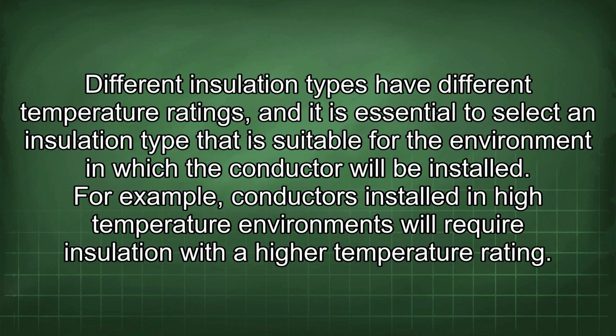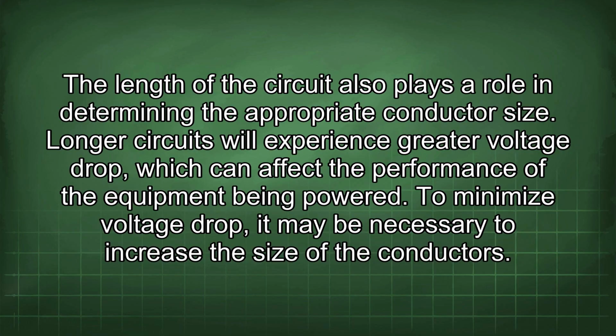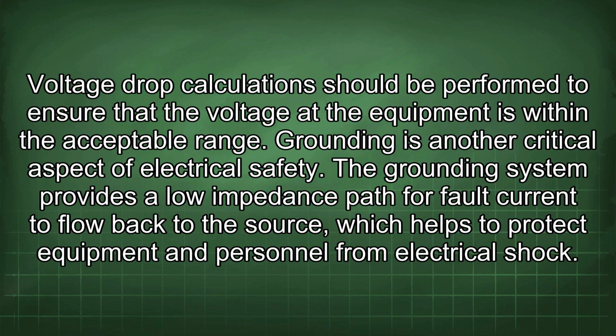The selection of the appropriate insulation type is also crucial. Different insulation types have different temperature ratings, and it is essential to select an insulation type that is suitable for the environment in which the conductor will be installed. For example, conductors installed in high-temperature environments will require insulation with a higher temperature rating. The length of the circuit also plays a role in determining the appropriate conductor size. Longer circuits will experience greater voltage drop, which can affect the performance of the equipment being powered. To minimize voltage drop, it may be necessary to increase the size of the conductors. Voltage drop calculations should be performed to ensure that the voltage at the equipment is within the acceptable range.